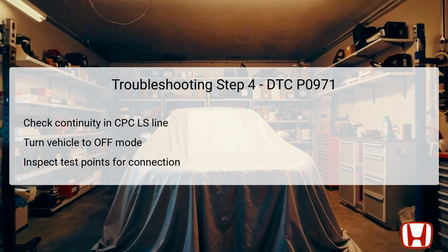This procedure ensures that the electrical path is uninterrupted, which is vital for the solenoid's operation. If continuity exists, proceed to the next troubleshooting step, confirming that the wiring is connected correctly. If continuity is not present, an open circuit in the CPC-LS line must be repaired, ensuring the complete electrical path is restored for optimal performance.